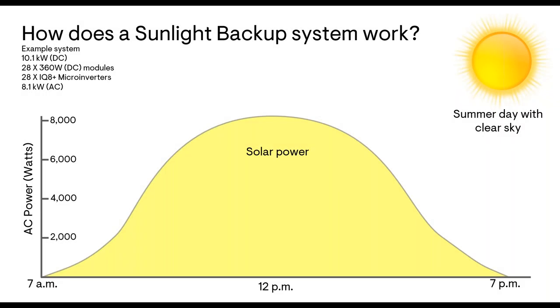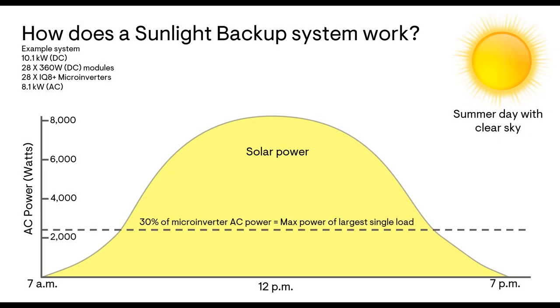I don't think you would ever hear anyone at Enphase say, let's do sunlight backup for an AC or motor load. It likely isn't going to be a good configuration. So when you're putting just the low loads on there, some lights, some outlets, fridge, things like that, you're keeping this power demand line as low as possible, which means you have the widest amount of time throughout the day where you're likely to have more solar production than demand in the house. If you have questions on that, let me know. Again, the lower you can keep this line, the more time throughout the day you'll be able to use a PV-only system.